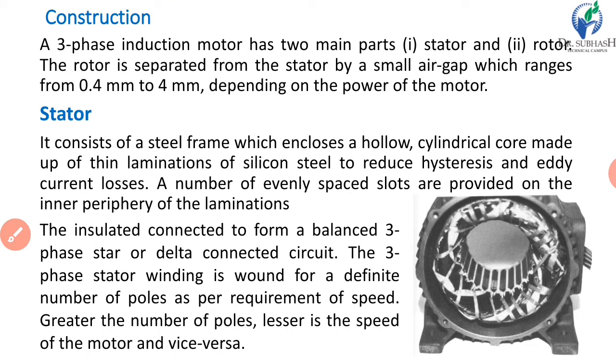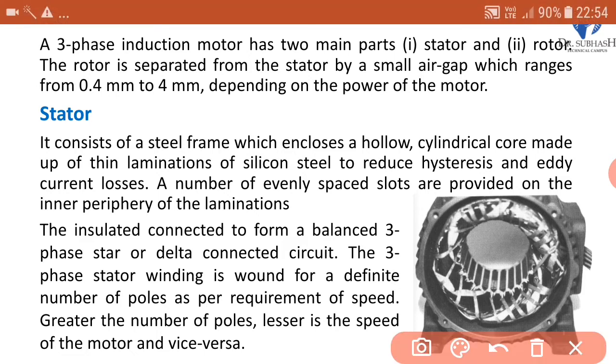Now construction. A three-phase induction motor has mainly two parts. One is the stator and the other is the rotor. The rotor is separated from the stator by a small air gap which ranges from 0.4 mm to 4 mm depending on the power of the motor. It means if the motor is small, then there is a small air gap, and for large power motors the air gap will be more.